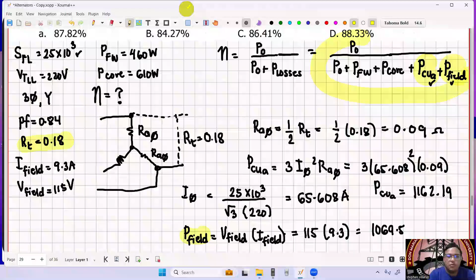Efficiency is equal to our output power. It's rated at 0.84 power factor, so this is 25 kilo multiplied by power factor of 0.84, all over 25 kilo times power factor 0.84 plus our friction and windage 460, plus our core loss 610, plus our armature copper loss of 1,162.19, plus our field copper loss of 1,069.5. So this is now equal to what?